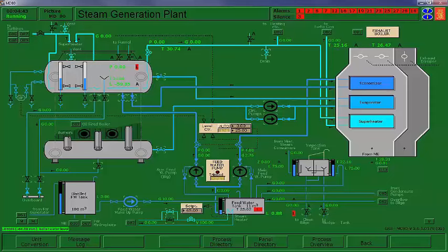Now, once that's done, we can go ahead and put the level controller in auto, and we'll leave the set point at mid-drum with the feed pump on. We're not producing any steam right now, right? And if I leave this on, there's always a small amount of leakage past that feed water regulating valve. So a small amount of water would be going into that drum, and it would be drifting the level up. And what you would find in real life, we've seen this happen multiple times, where they leave that on and your level gets up and you trip on high level. So leave it off until this starts producing steam.